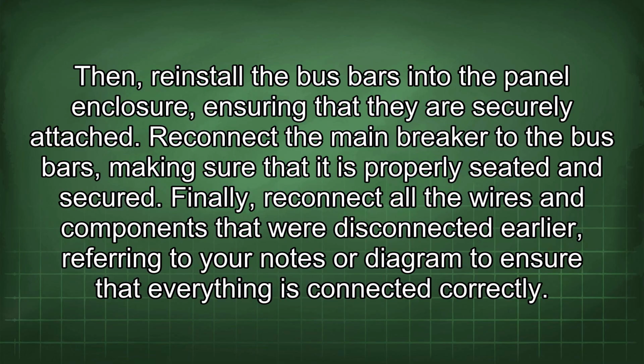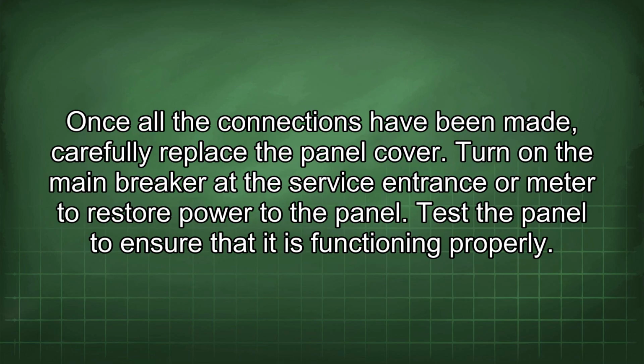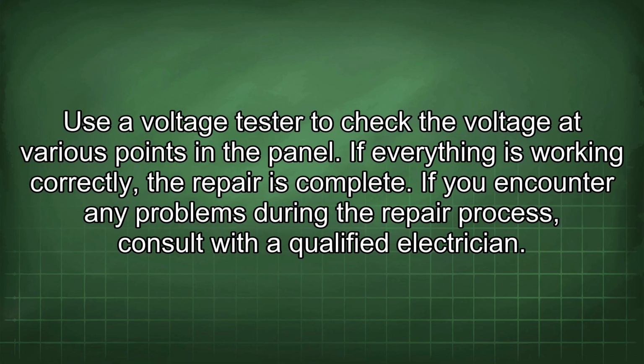Finally, reconnect all the wires and components that were disconnected earlier, referring to your notes or diagram to ensure that everything is connected correctly. Once all the connections have been made, carefully replace the panel cover. Turn on the main breaker at the service entrance or meter to restore power to the panel. Test the panel to ensure that it is functioning properly. Use a voltage tester to check the voltage at various points in the panel. If everything is working correctly, the repair is complete.